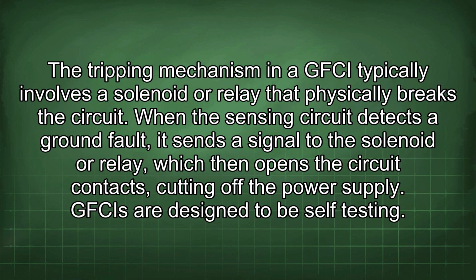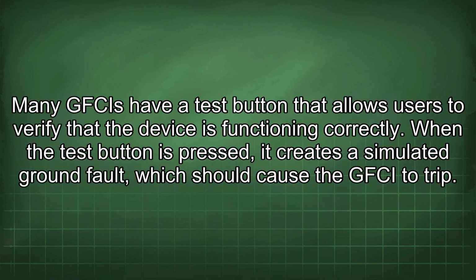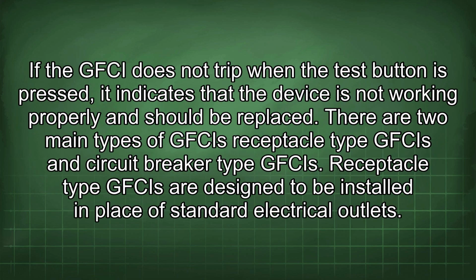The tripping mechanism in a GFCI typically involves a solenoid or relay that physically breaks the circuit. When the sensing circuit detects a ground fault, it sends a signal to the solenoid or relay, which then opens the circuit contacts, cutting off the power supply. GFCIs are designed to be self-testing. Many GFCIs have a test button that allows users to verify that the device is functioning correctly. When the test button is pressed, it creates a simulated ground fault, which should cause the GFCI to trip. If the GFCI does not trip when the test button is pressed, it indicates that the device is not working properly and should be replaced.